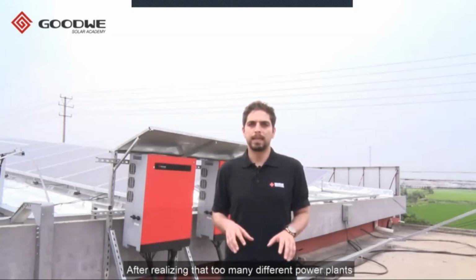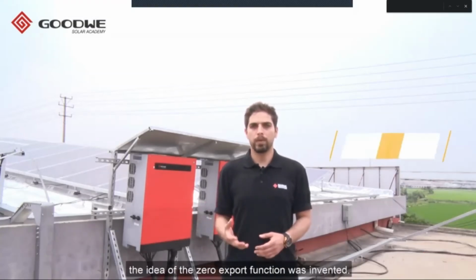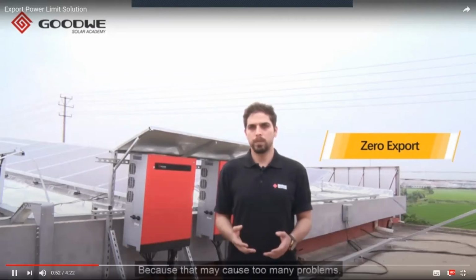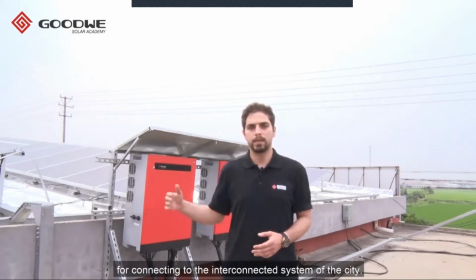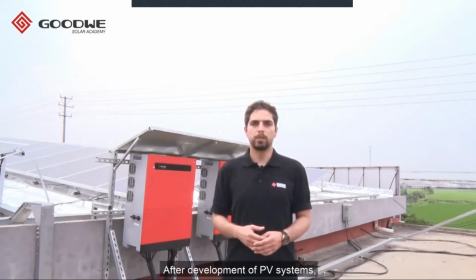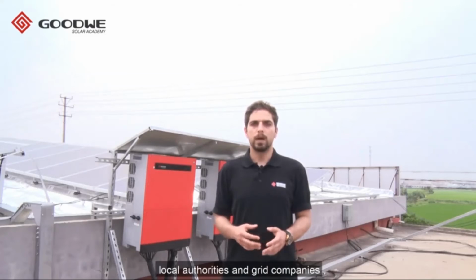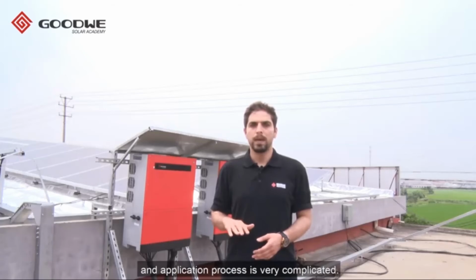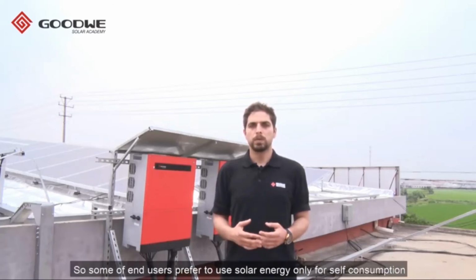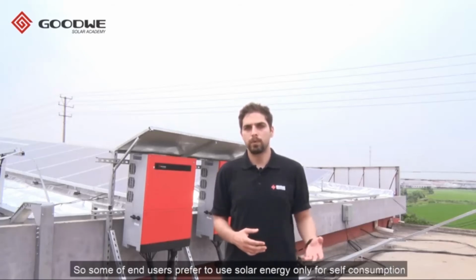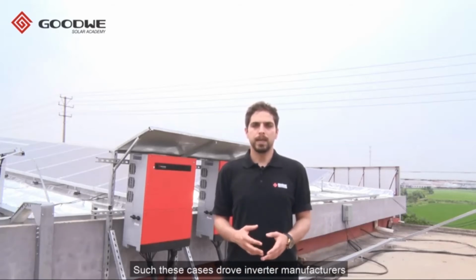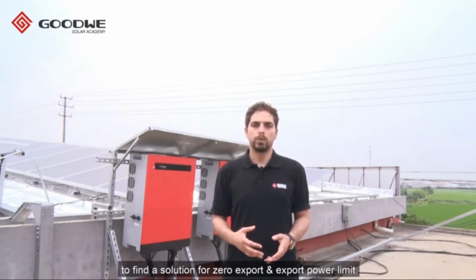First, we should know why we have these features. After realizing that too many different power plants cannot directly connect to the grid, the idea of the zero export function was invented, because that may cause too many problems. Therefore, countries and grid companies set some rules for connecting to the interconnected system of the city. After the development of PV systems, the local authorities and grid companies made some regulations for selling electricity. But in some areas, the FITs are very low and the application process is very complicated. So some end users prefer to use solar energy only for self-consumption instead of selling it. Such cases drove inverter manufacturers to find a solution for zero export and export power limit.